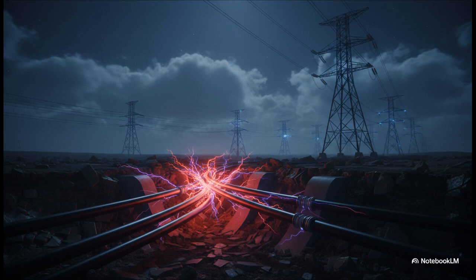As we shift to renewables and rely heavily on long underground cables, we dramatically increase the grid's capacitance. This lowers our resonance frequencies, making the grid highly vulnerable to parallel and series resonances. Ironically enough, those old-school overhead lines are actually much safer when it comes to defending against these high-frequency harmonic attacks.